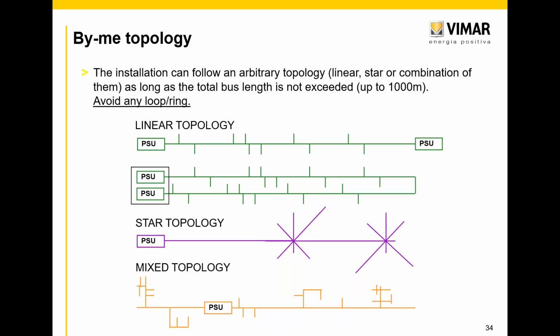Or 2 power supplies in the panel board, the second sketch, where the 2 power supplies are physically in one place but supply the system like a linear topology. So remember, do not make a bridge, do not connect 2 power supplies immediately in parallel, to prevent problems.